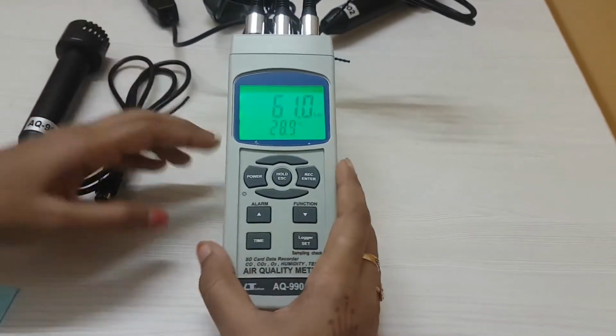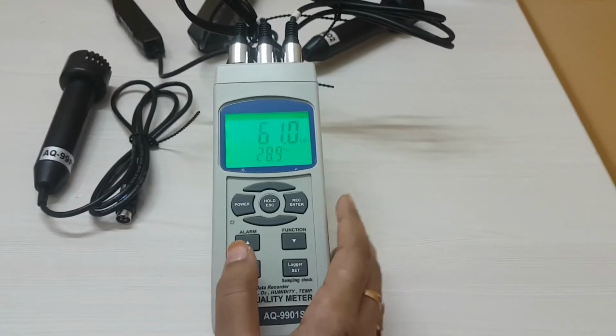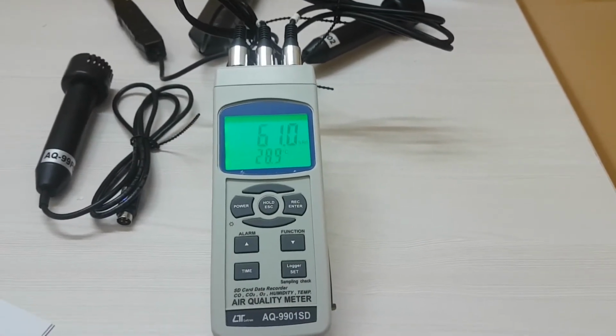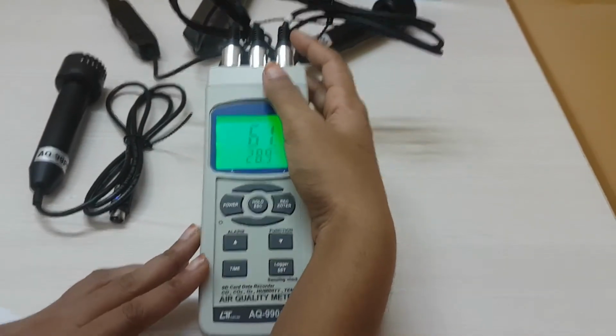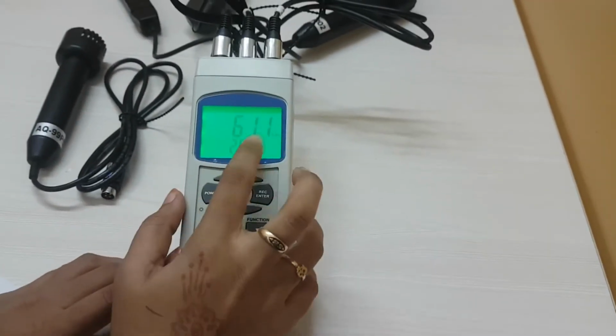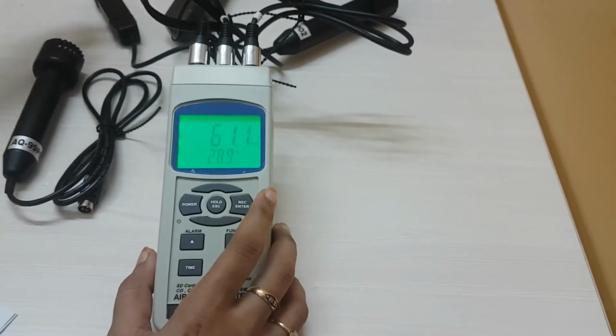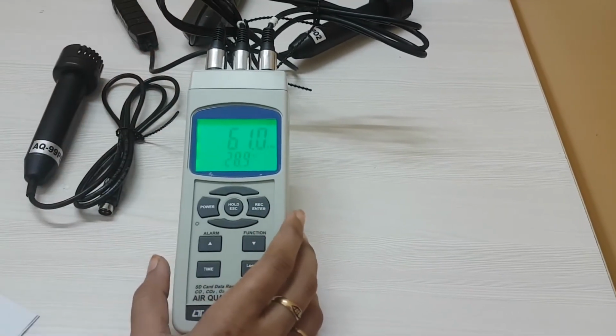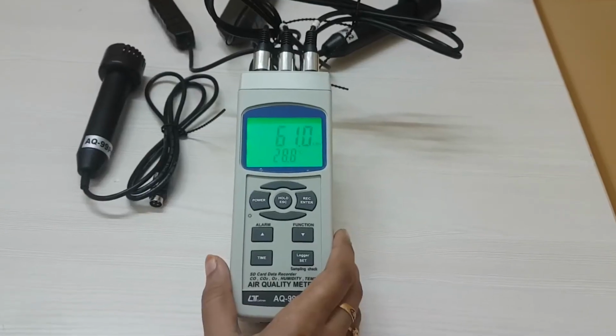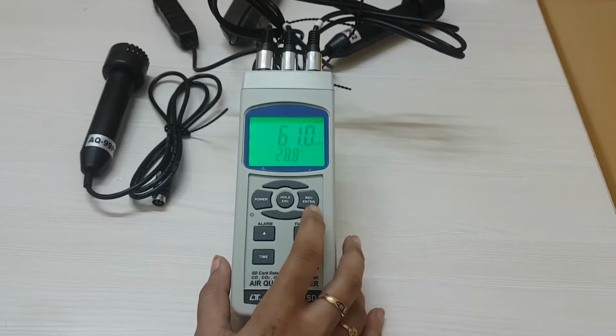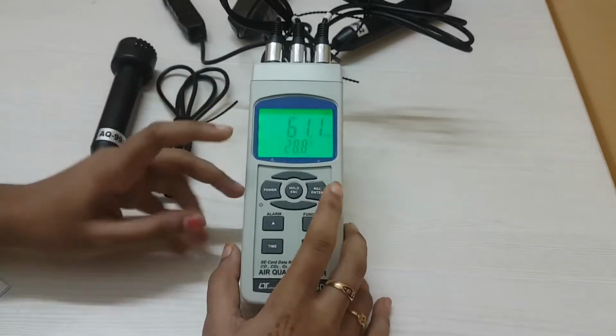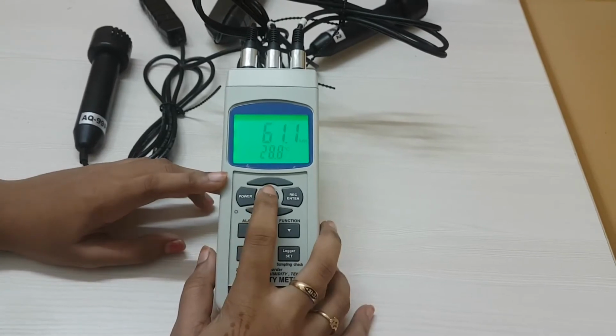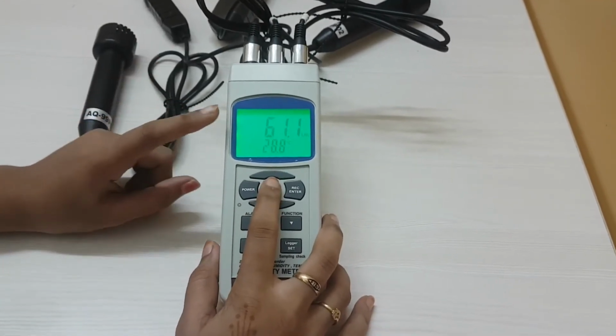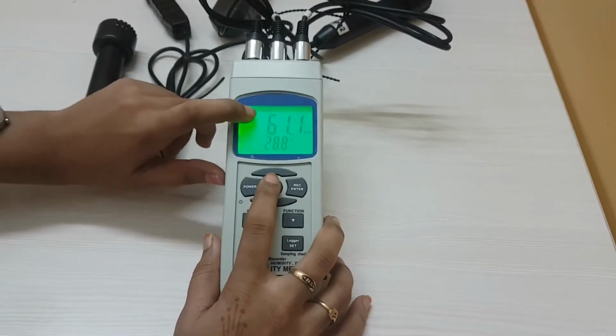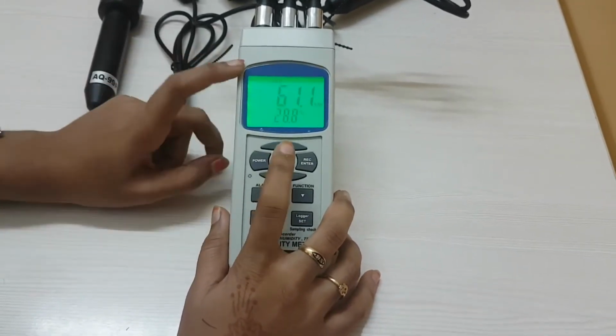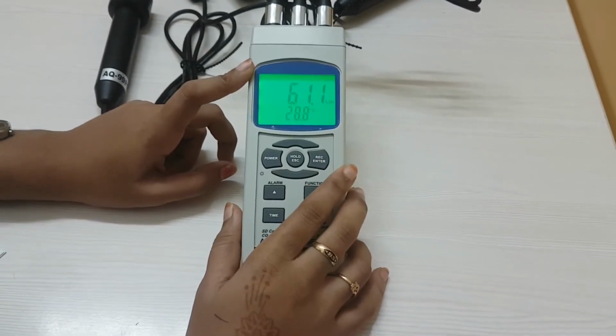Coming to this, I have already explained to you about the probes. Now getting into the working function, the meter can plug in maximum 3 probes at the same time, but it can show only one monitoring unit. Either it may be humidity or CO2, or it may be other. We do have data holding function also. During the measurement, just press the hold button, and it will hold the measured value, and the LCD screen will show a display as hold. You can see this here. It is the held value 61.1. Now it is in reading mode.